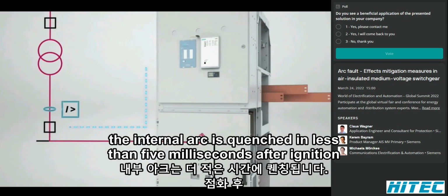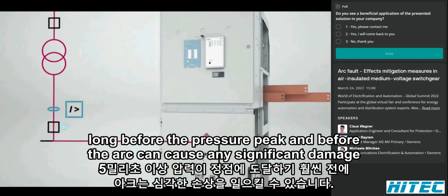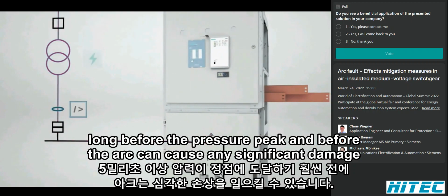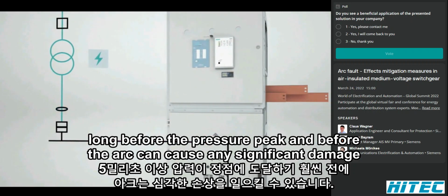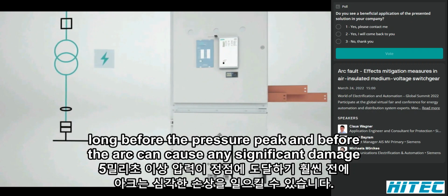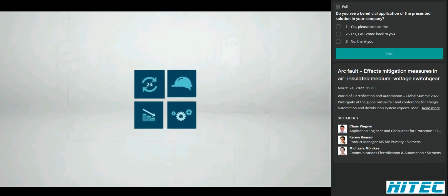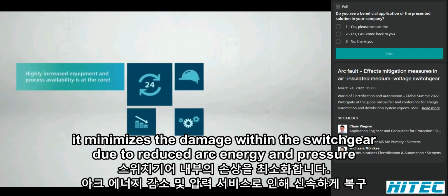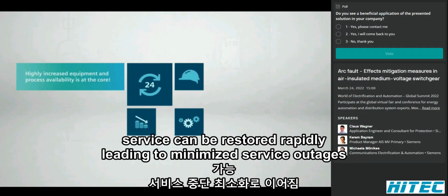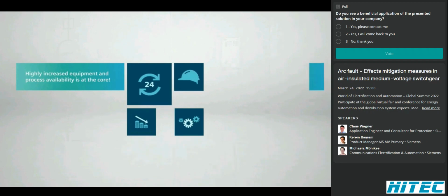The internal arc is quenched in less than 5 milliseconds after ignition, long before the pressure peak and before the arc can cause any significant damage. It minimizes the damage within the switchgear due to reduced arc energy and pressure. Service can be restored rapidly, leading to minimized service outages.